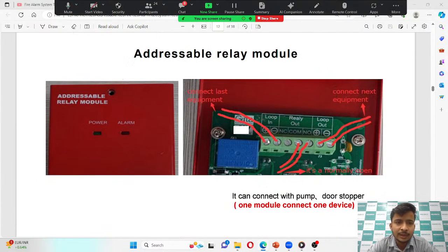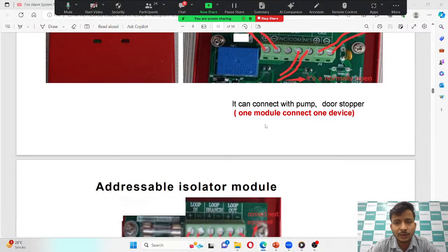Then the addressable relay module. It has 3 ports. One is loop in, another one is loop out, and the third one is relay out. And relay out has both options, normally open and normally closed. So if you want to connect it with the PA system, you need to connect normally open and common with the PA system trigger input or the relay input. If you want to connect with a pump or door stopper or anything, you can use it as per that scenario, whatever it has. If it has normally open, then you need to use normally close. So as per that, you need to select.